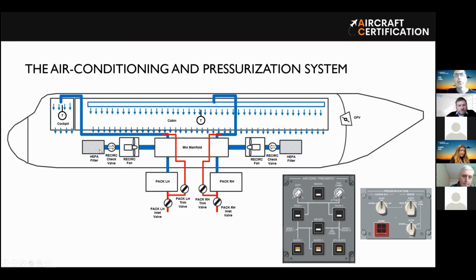But a HEPA filter is not good for volatiles, for example vapors and some smokes, some level of particles of smoke. HEPA filter is mainly not good for volatiles. But volatiles are not exactly a problem. If we detect the smoke, we can shut down the recirculation fan. This can avoid these volatiles ingressing into the cabin, because volatiles can be detected by a smoke detector. So if we have a failure in the bay, we will shut down the recirculation fan. That's it.